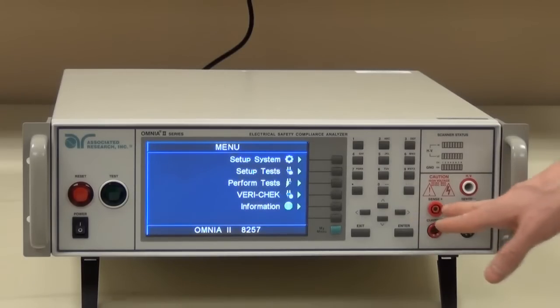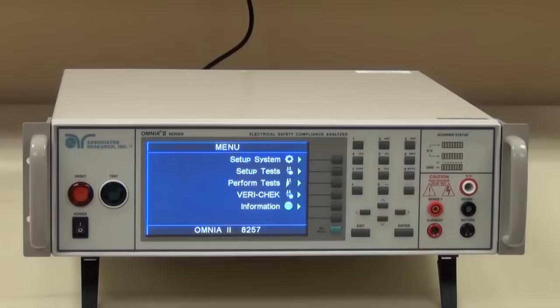The Sense Plus and Sense Minus ports are used for what is known as a 4-wire Kelvin measurement. What this does is it senses the voltage drop across the circuit and allows you to negate the resistance of the test leads. And finally, the return port is going to be your return path for your ground bond, DC continuity, high pot, and insulation resistance tests.